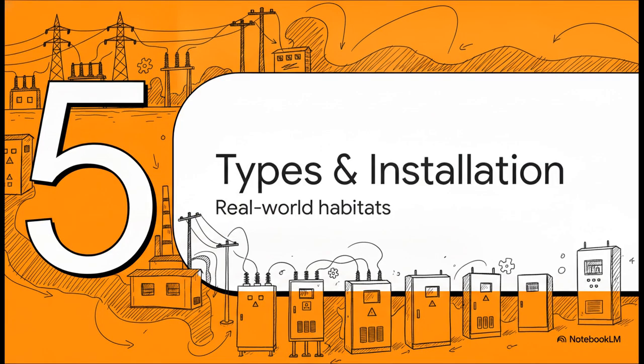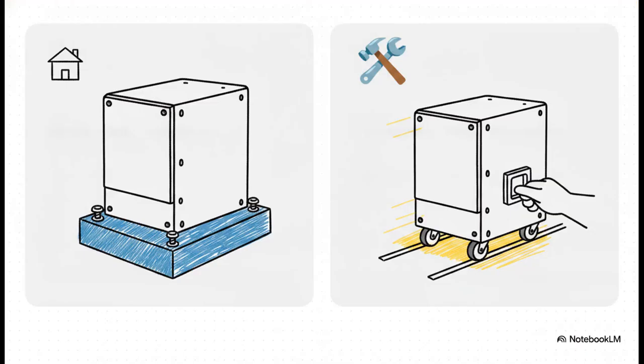Okay, Section 5, VCB types and installation. Let's look at the real-world habitats. Generally, you're going to see VCBs in two main form factors. The fixed type is exactly what it sounds like, permanently installed right into the switchgear panel. These are usually much larger and built for incredibly high capacity. On the other hand, the draw-out type is mounted on rails or wheels. This design means the entire heavy breaker unit can be physically rolled out of the panel for inspection and maintenance. So it trades a bit of that permanence for incredible flexibility and safety.